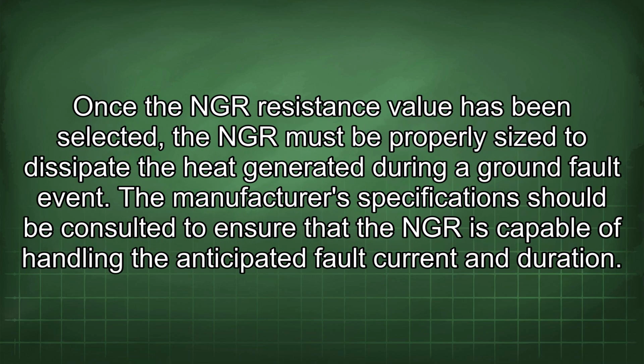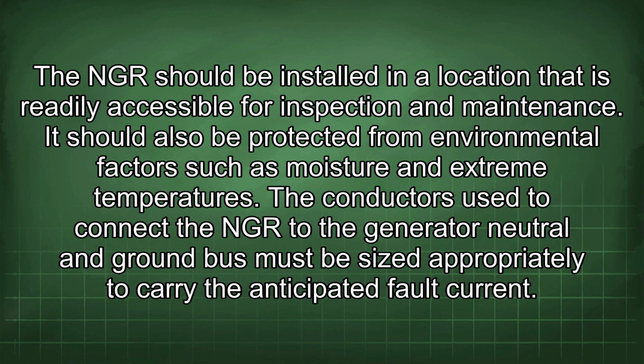Once the NGR resistance value has been selected, the NGR must be properly sized to dissipate the heat generated during a ground fault event. The manufacturer's specifications should be consulted to ensure that the NGR is capable of handling the anticipated fault current and duration. The NGR should be installed in a location that is readily accessible for inspection and maintenance. It should also be protected from environmental factors such as moisture and extreme temperatures.